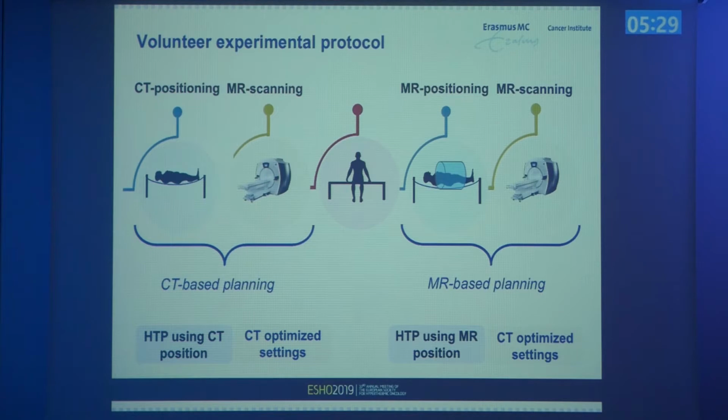So we do the treatment planning first using the CT position, we optimize the antenna settings, and then in the MR-based planning, we also do the treatment planning using this position, and then we apply the same antenna settings in order to compare.